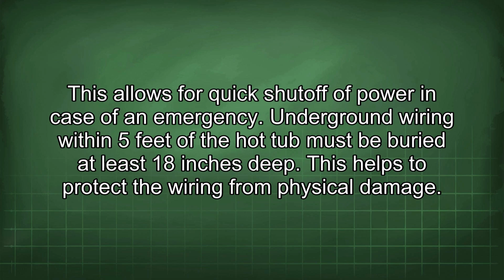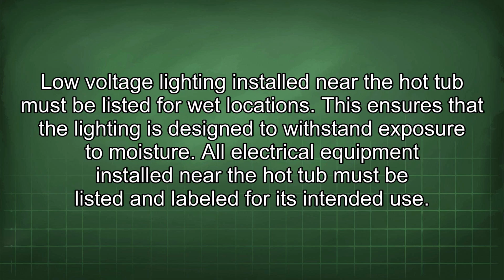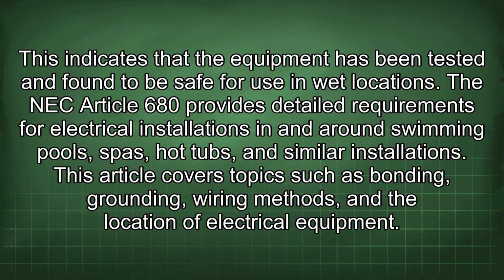Underground wiring within 5 feet of the hot tub must be buried at least 18 inches deep. This helps to protect the wiring from physical damage. Low voltage lighting installed near the hot tub must be listed for wet locations. This ensures that the lighting is designed to withstand exposure to moisture. All electrical equipment installed near the hot tub must be listed and labeled for its intended use. This indicates that the equipment has been tested and found to be safe for use in wet locations.